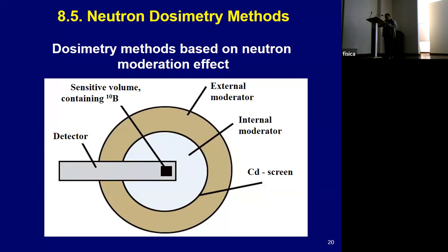In some cases, nevertheless, it may be necessary to measure the neutron spectrum. For example, when it is necessary to clarify the parameters of biological protection. For this, neutron dosimeters and spectrometers with a set of moderators in the form of spheres of various diameters are used. They are the so-called Bonner spheres. Such a spectrometer is called a multi-sphere spectrometer. Measurement of the neutron spectrum makes it possible to more accurately estimate the ambient dose equivalent rate.